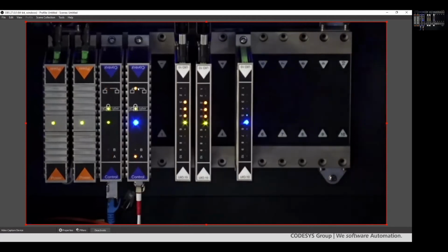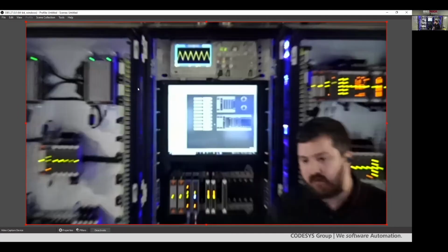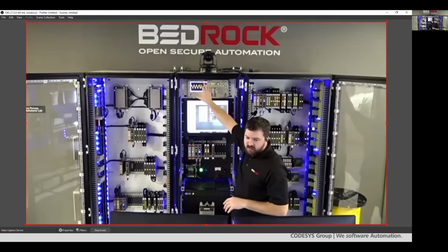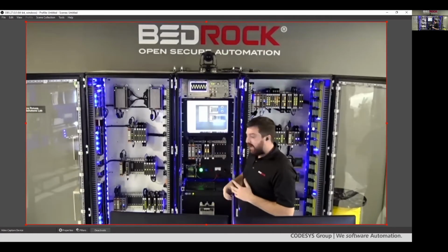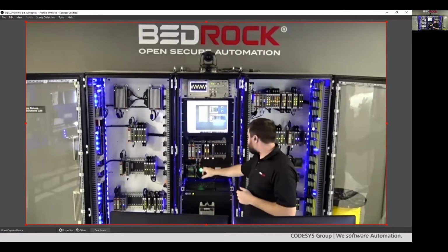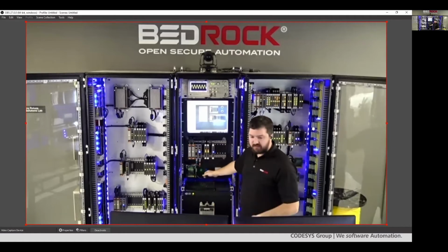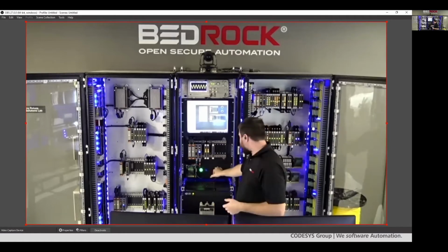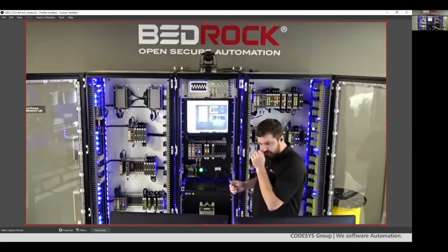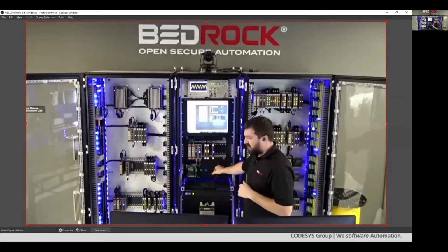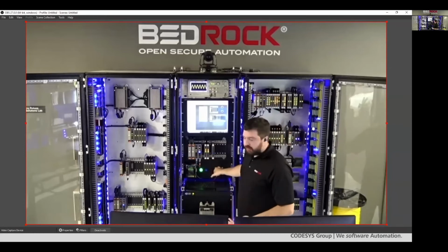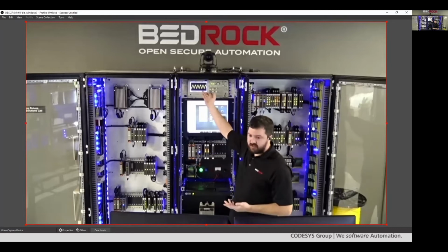One other thing we like to point out is, okay, that's one thing to show that the controller is switching over, but we also like to show that data is actually being updated. So up here, you'll see we have this redundant I/O running out to a small panel. We have some digital outputs as well as analog outputs, and this is actually driving a 4-20 output, which is giving us a triangle wave up top here.